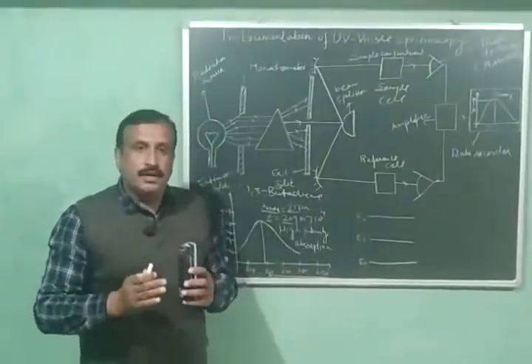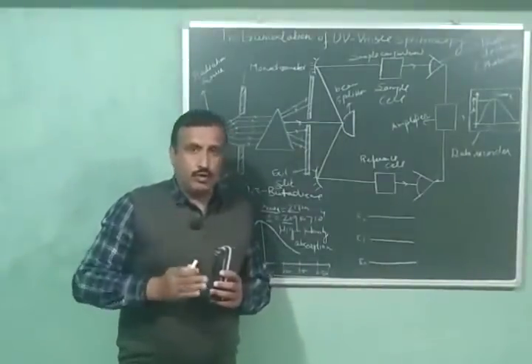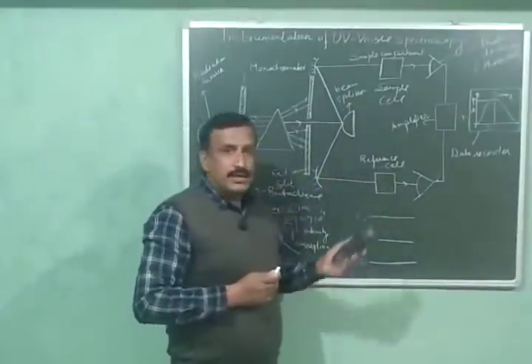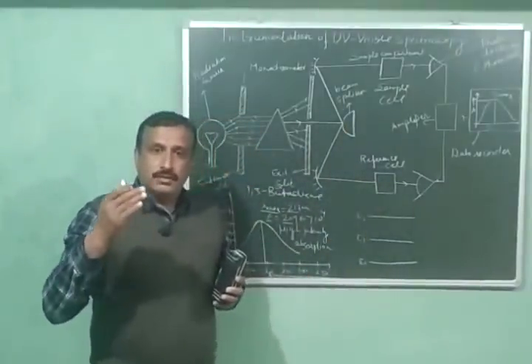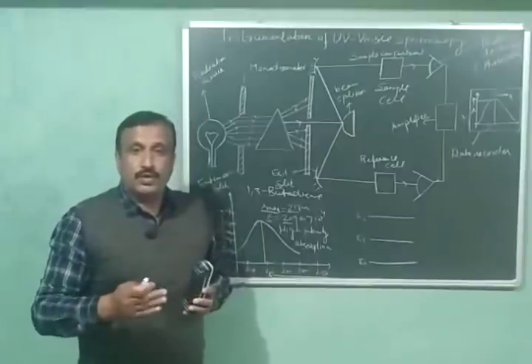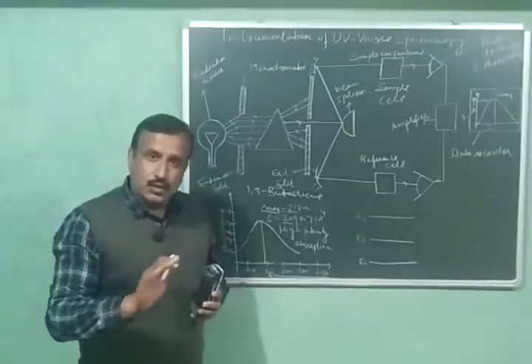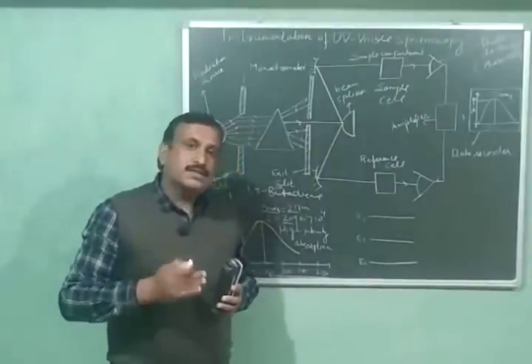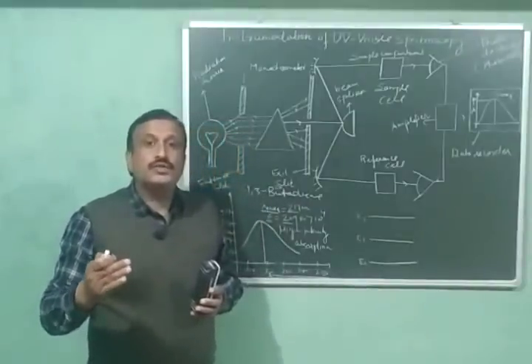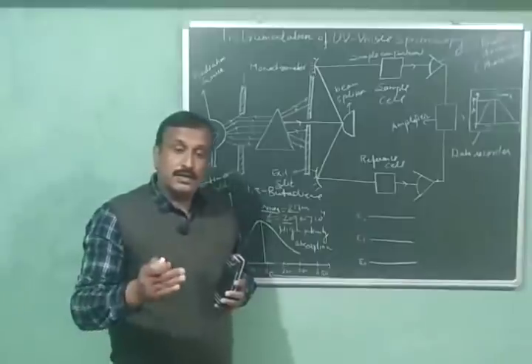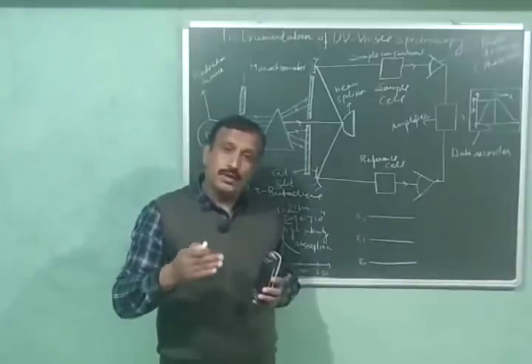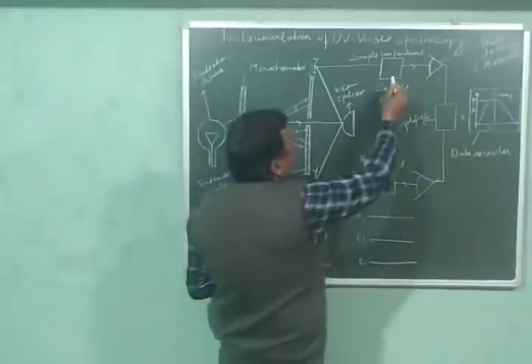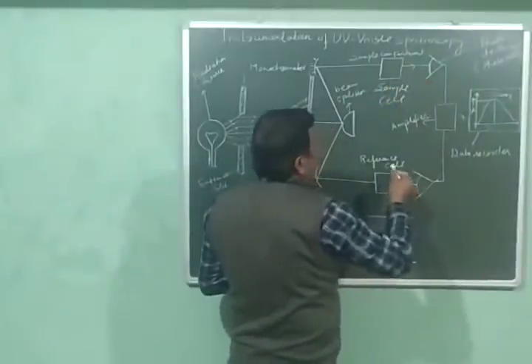The second beam is passed through the reference cell, which contains pure solvent only. The sample cell and the reference cell are made of silica or quartz, because silica or quartz do not absorb UV-visible radiations. Glass cells can be used only for visible light, because glass strongly absorbs UV radiations.